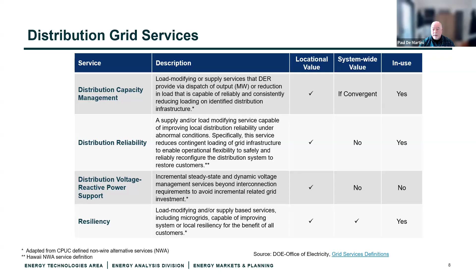Distribution voltage and reactive power support hasn't been done as a separate contract, to my knowledge, or service beyond what's been embedded as a requirement in interconnection standards for adhering to IEEE standard 1547/2018 for certain aspects of voltage and reactive power management. Distribution capacity management has been the primary service used for non-wires alternative procurements in the U.S. to date, and continues to be.